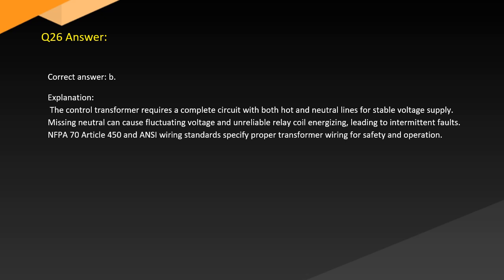Answer. Correct answer: B. Explanation. The control transformer requires a complete circuit with both hot and neutral lines for stable voltage supply. Missing neutral can cause fluctuating voltage and unreliable relay coil energizing, leading to intermittent faults. NFPA 70 Article 450 and ANSI wiring standards specify proper transformer wiring for safety and operation.